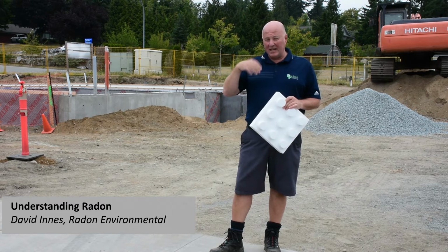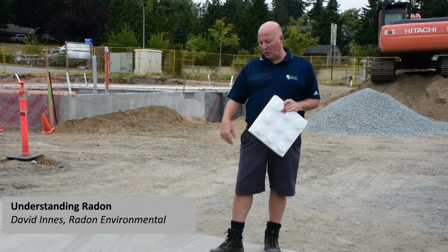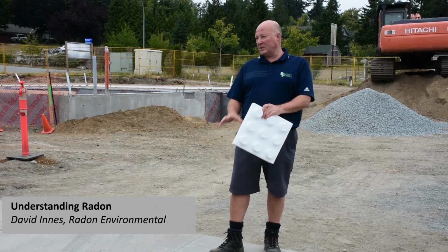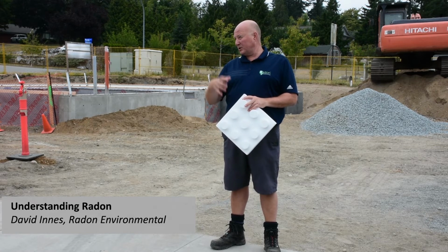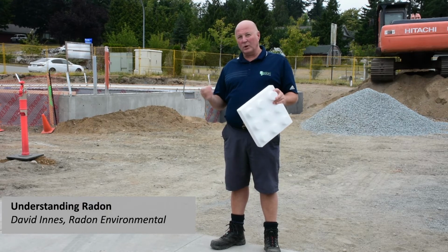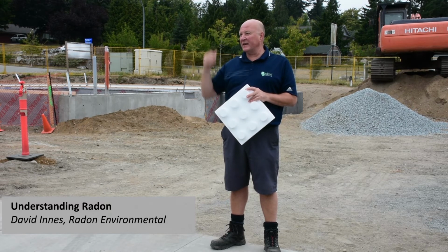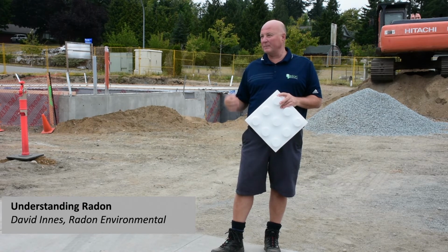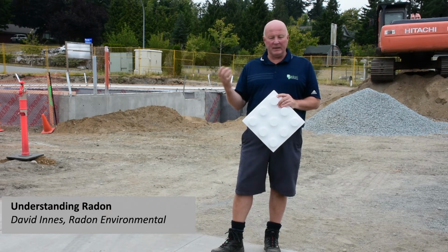We would go into an existing house that had tested high. We'd core a 5-inch hole in the slab in the basement, dig out a little bit of the fill or gravel underneath, and then put a vacuum test on that and drill some communication holes across the slab and put suction on that to see what kind of pressure field extension we get. Assuming that works well, with one vent pipe, we'd install an inline radon fan, vent that to the outside, and that fan would run 24/7 and depressurize the slab so that we get that favorable pressure differential that I spoke about, and that eliminates the radon.